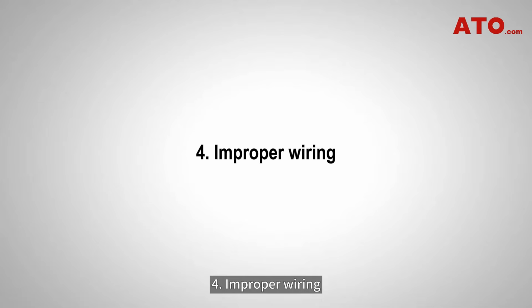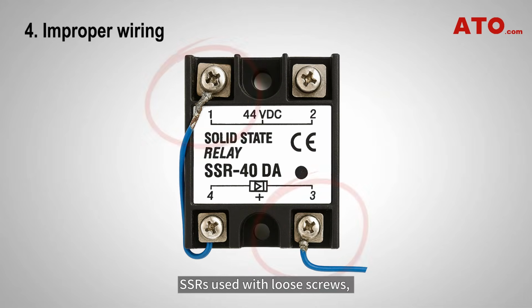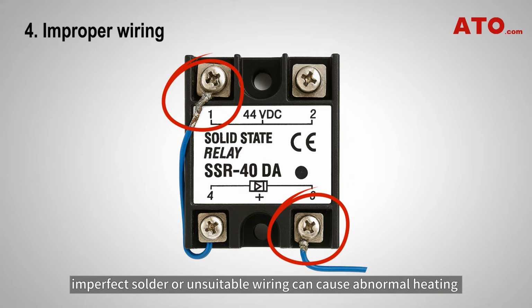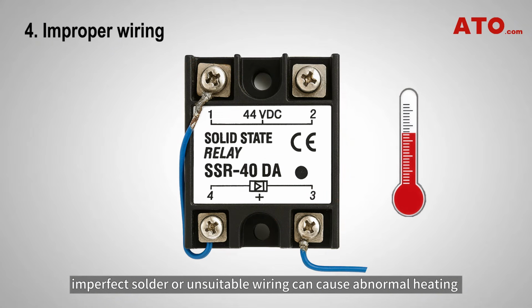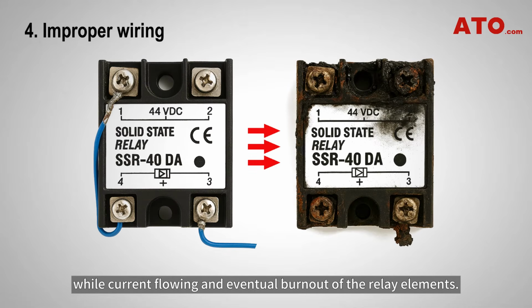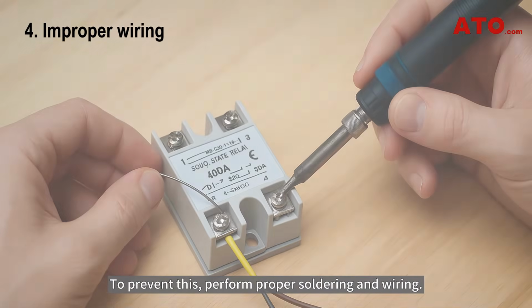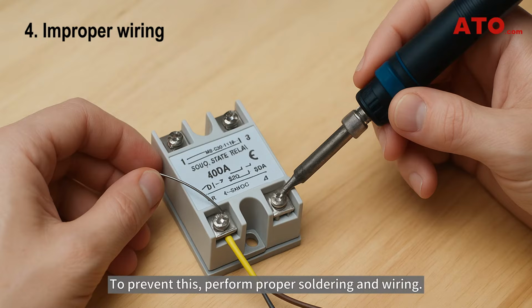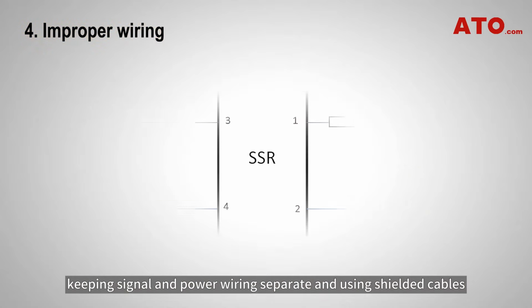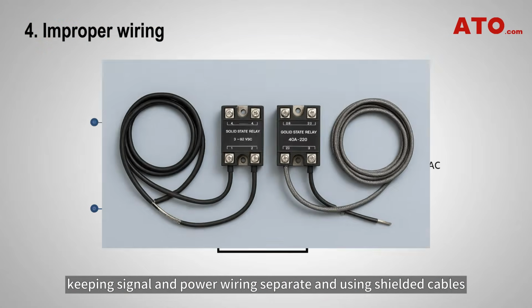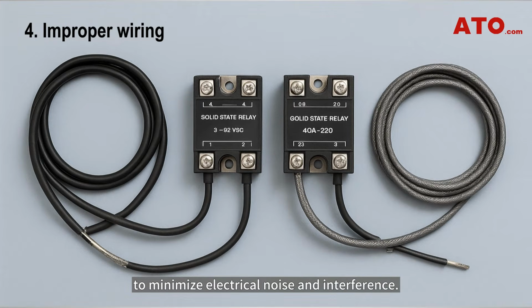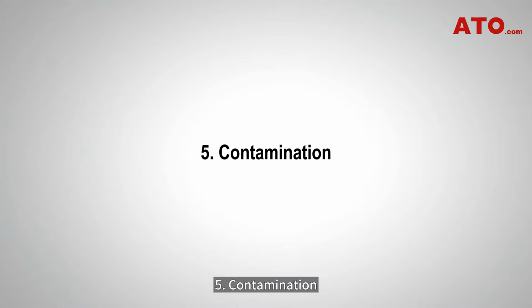Number 4. Improper wiring. SSRs used with loose screws, imperfect solder, or unsuitable wiring can cause abnormal heating while current is flowing and eventual burnout of the relay elements. To prevent this, perform proper soldering and wiring. You can take it a step further, keeping signal and power wiring separate and using shielded cables to minimize electrical noise and interference.